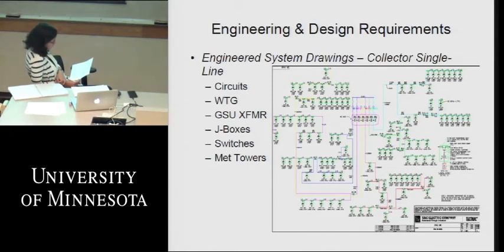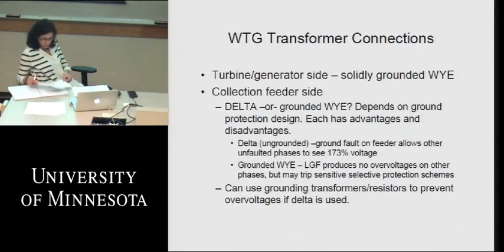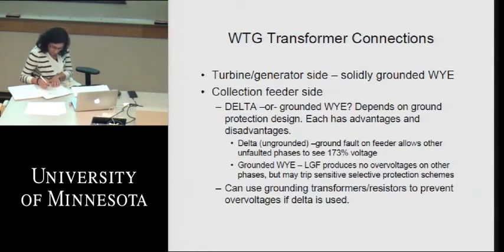The transformer on the wind turbine can be configured for either a delta connection or a Y connection on the medium voltage collection side here. I know we're getting close to the end here, so I'm trying to speed it up a little bit. Generally on the wind turbine, it's always a solidly grounded Y connection. But on the collection side, it could be a delta or a grounded Y. This really depends on the ground protection philosophy of the particular designer. You've got to pick one or the other and then accommodate the rest of your ground fault protection based on whether you pick a delta or a Y connection on those transformers.